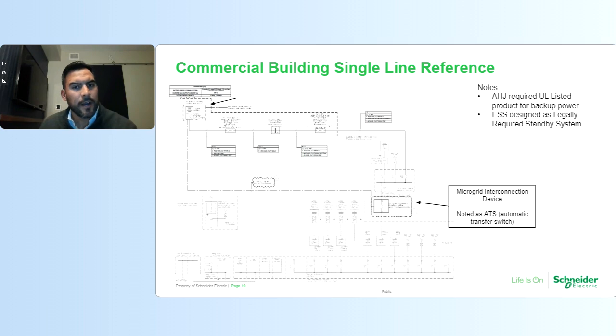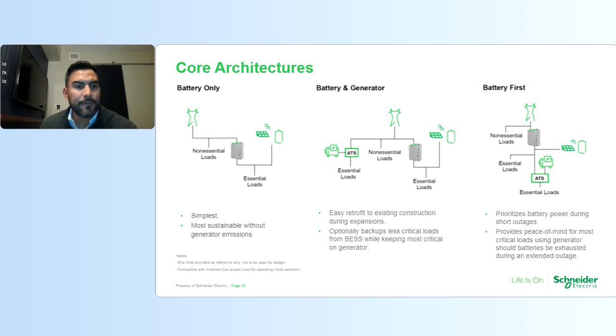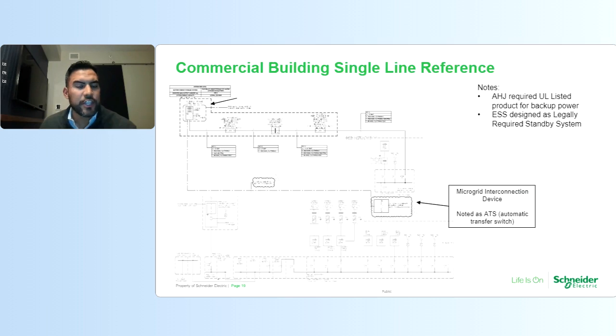This is another opportunity that we've worked on with a client. This is for a commercial building. In this facility, they use the energy storage system as a backup power source, specifically for an elevator system. And you can see they're highlighted in the bubbles to the left. That's the microgrid interconnection device. This is a 1200 amp service. So you can see at the bottom, we have a 1200 amp service. One of the breakers is feeding SourcePack, and then upstream of SourcePack is this panel board where you have the energy storage system and an elevator circuit connected.